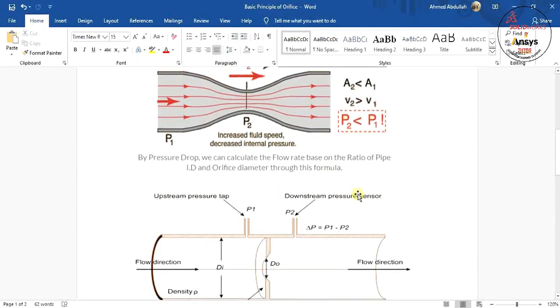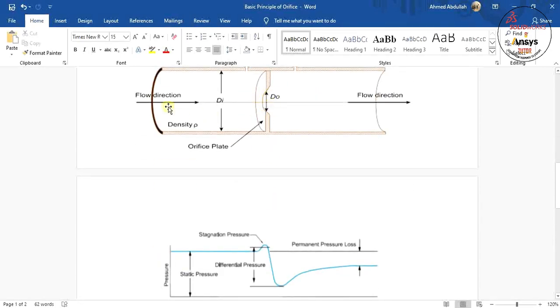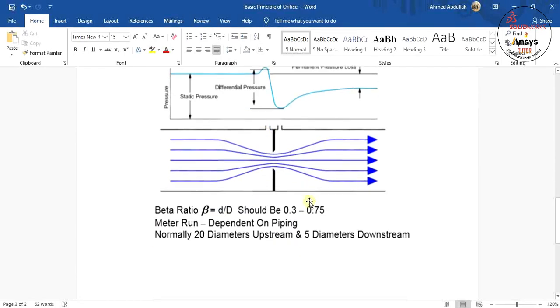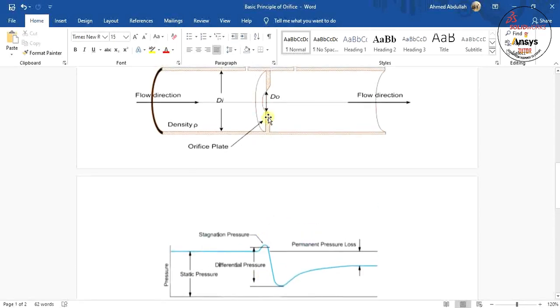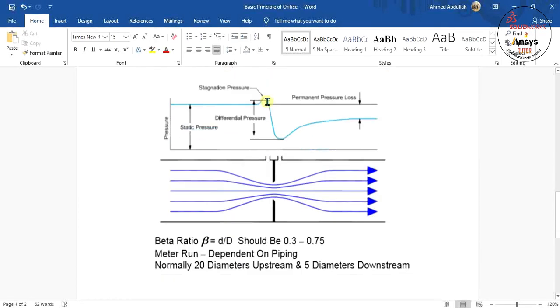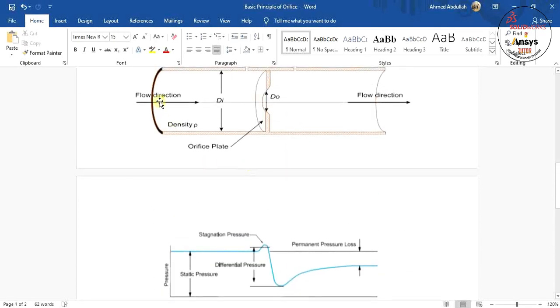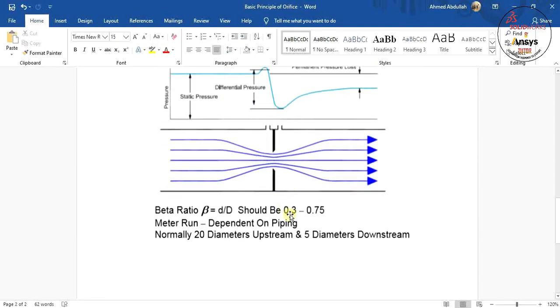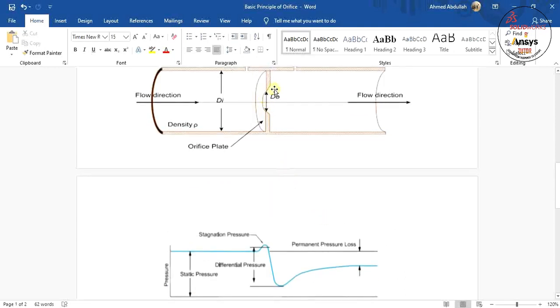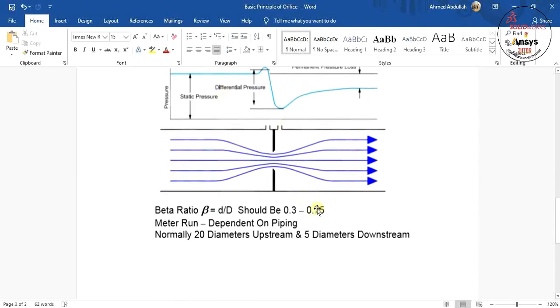So how do we measure the outer diameter and inner diameter? There is a formula: the beta ratio is equal to small d divided by capital D, where small d is the orifice plate diameter and capital D is the pipe diameter. This ratio should be between 0.3 to 0.75. We are going to use 10 centimeters for the orifice diameter and 20 centimeters for the pipe diameter, giving a beta ratio of 0.5, which is within the valid range.